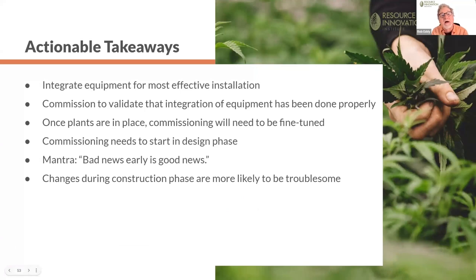I had a great story about commissioning with Priva. We had kind of ghosts in the machine, as I call it, these weird little alarms, like power outage alarms. Priva came through the commissioning and found that our electronics subcontractor hadn't tightened down the terminal screws for some of the equipment's wires, so it was totally random. I would have found it eventually, but it took a professional commissioner to know to look for something like that. Anyway, I should stop talking.